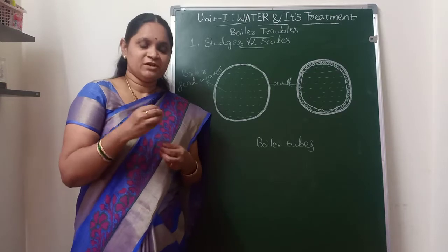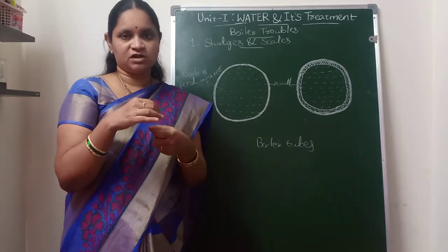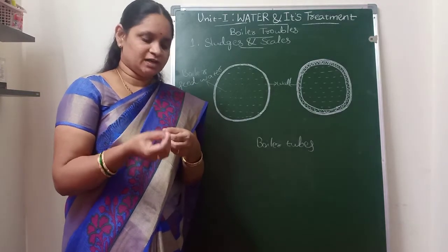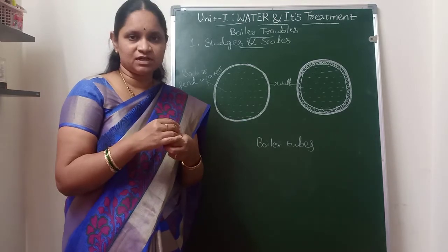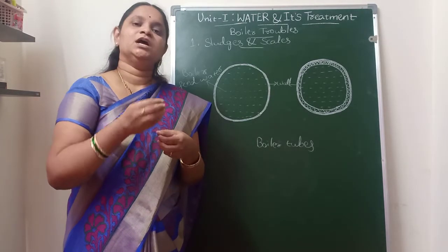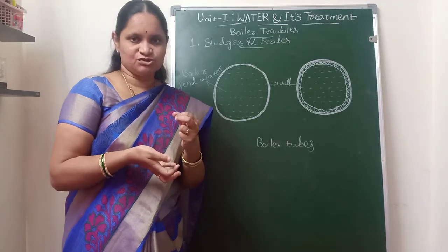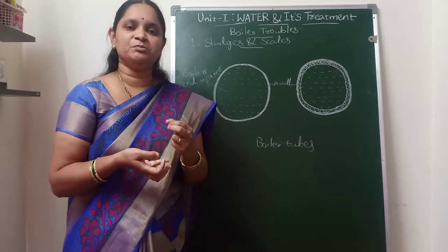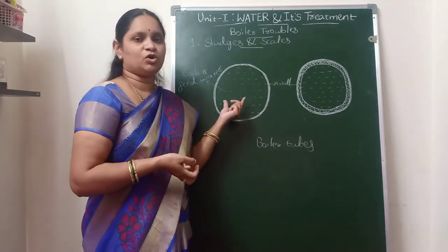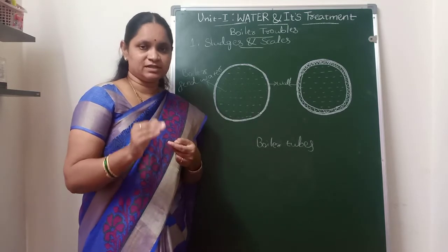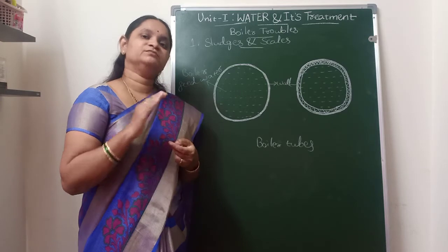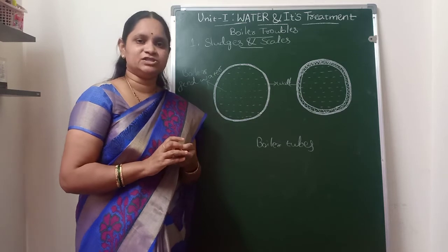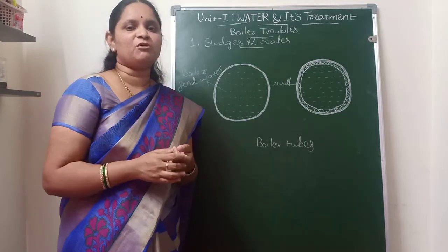Like when we are adding some amount of salt to the water in a glass, initially the salt will dissolve. And if you add more and more salt, some amount of salt will remain undissolved, because there the ionic product is more than the solubility product. In the same way, in the boiler feed water also, after reaching some concentration, the ionic product of the salts will increase beyond the solubility product. At that condition, all the dissolved salts will be thrown out in the form of precipitates.